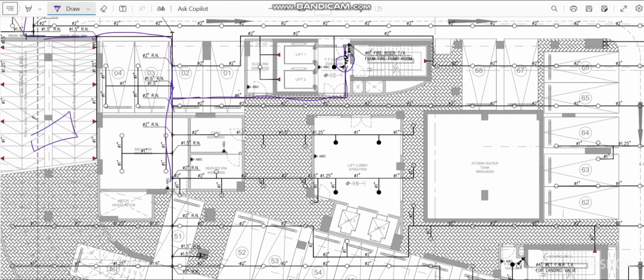Because the area is very high, we cannot use the tree type of arrangement. In the tree type arrangement, one common cross main will come from there, and two branches will come like this. One side maximum 8 sprinklers, another side maximum 8 sprinklers only we can provide, and additionally 2 more sprinklers, like a maximum of 10 sprinklers with some additional condition. But in the loop system you can provide plenty of sprinklers. That is the reason we followed the loop system here, because of the huge area.